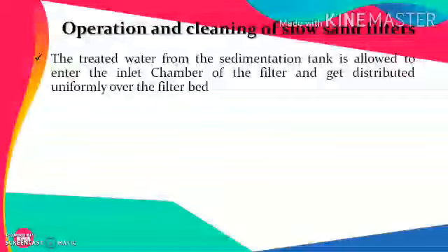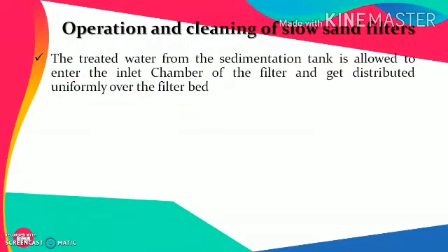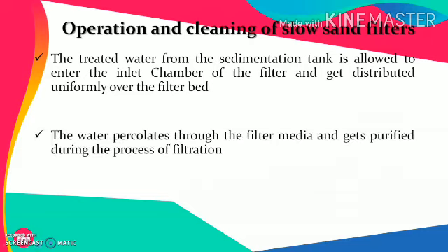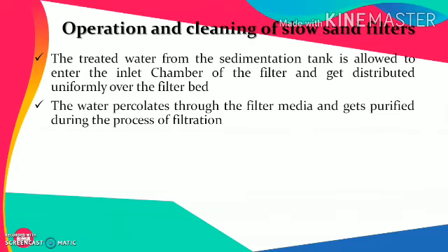The operation and cleaning of the slow sand filters. The treated water from the sedimentation tank is allowed to enter the inlet chamber of the filter, and then it gets distributed uniformly over the filter bed. For that, generally a weir is provided. The water percolates through this filter media and gets purified during the process of filtration.